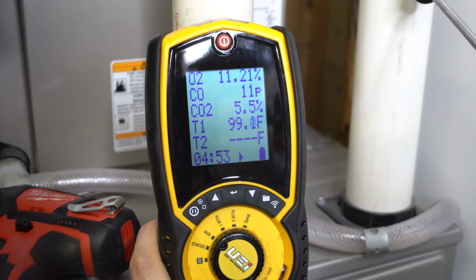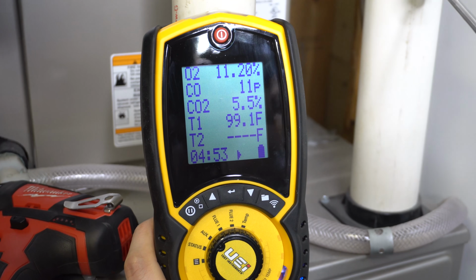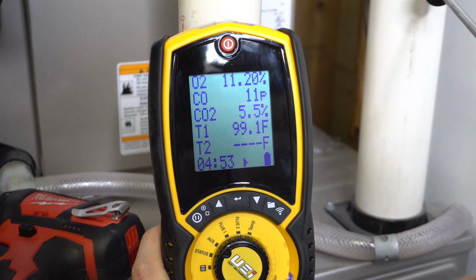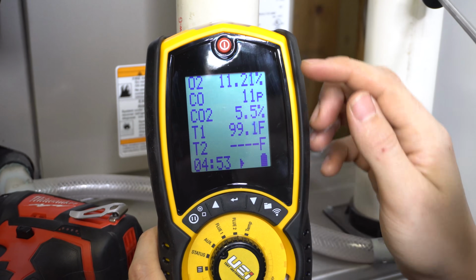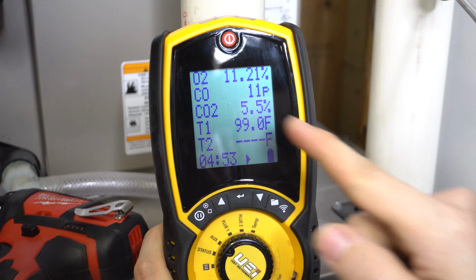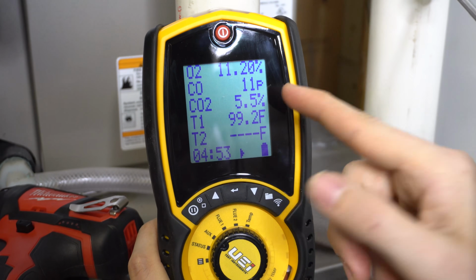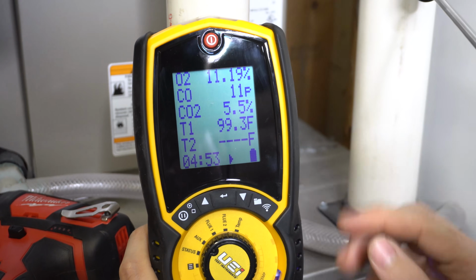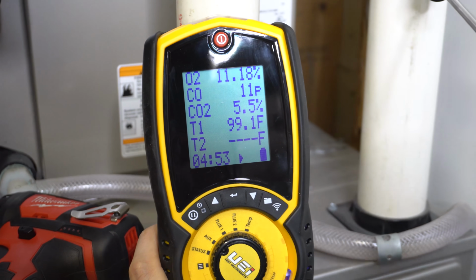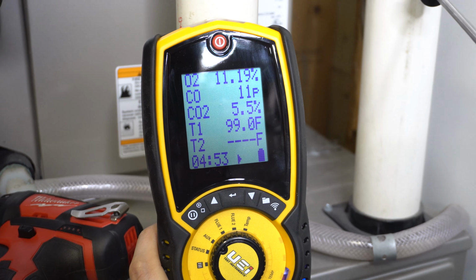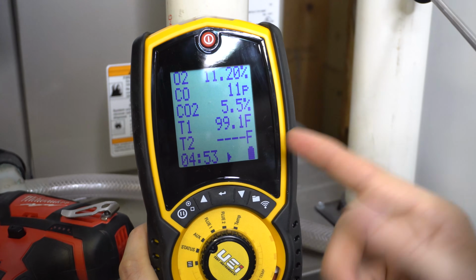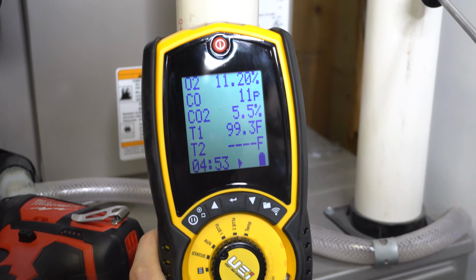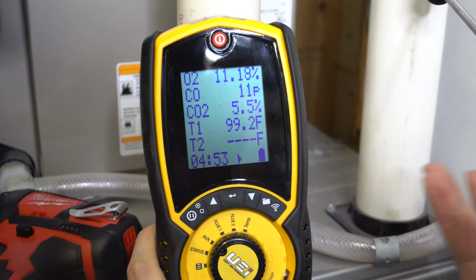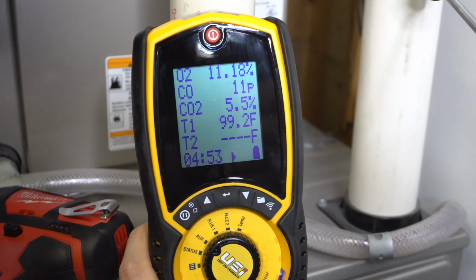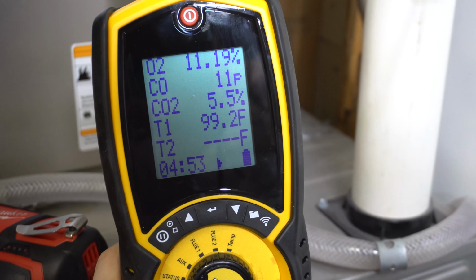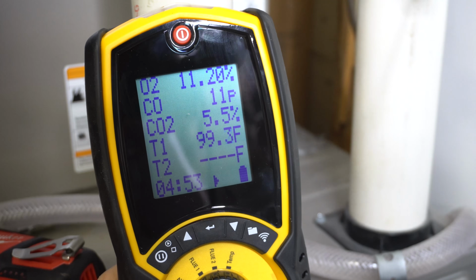It's been about 2 minutes now and the numbers have pretty much stabilized. 11% for the oxygen. Those are pretty normal levels. That's what I usually see for high efficiency furnaces. Carbon monoxide, 11 parts per million. That's actually very good. That's pretty low for a high efficiency furnace. A lot of times I'll see it somewhere around 35, 40, 50 parts per million. Carbon dioxide, that's pretty normal as well. Typically on high efficiency ones, I see it somewhere between 5 and 7%. And a 99.2 temperature inside of the exhaust pipe is pretty good as well.